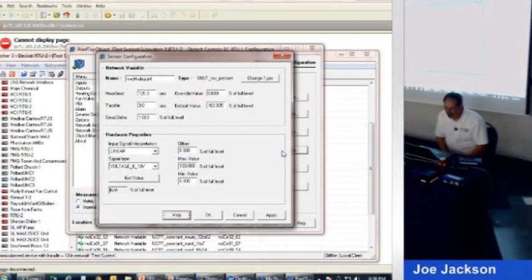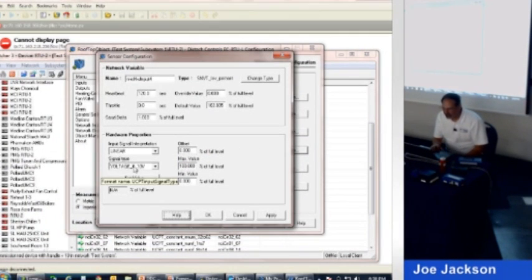So we'll throw a space humidity sensor on there and it'll auto set it for us. Configures the whole thing. But they make different kinds of humidity sensors, so let's see what it did. So it set it up as linear, and it set it up as 0 to 10 volts. At 10 volts, it's going to read 100%, and at 0 volts, it's going to read 0%. That's typical. Nothing spooky going on there.